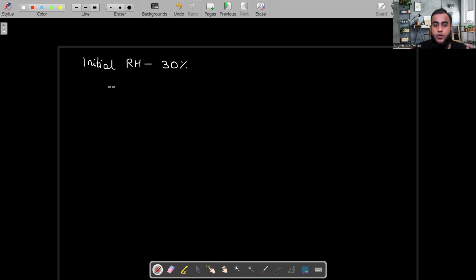Here you have to know the dry bulb temperature also for the location for which you are designing. Suppose for Hyderabad, as an example. Ambient temperature is important here for the humidifier selection. Sorry, I'm not talking about outside temperature. Inside the room, how much temperature do we have to maintain as per ASHRAE, as per human comfort? 23 degrees Celsius, and in Fahrenheit, near about, we can't say exact, but 76 plus minus 2 degrees Fahrenheit. So let's say I want to maintain 75 degrees Fahrenheit inside the room.